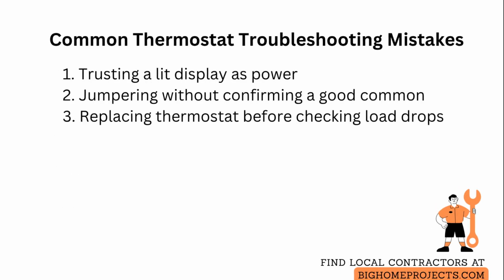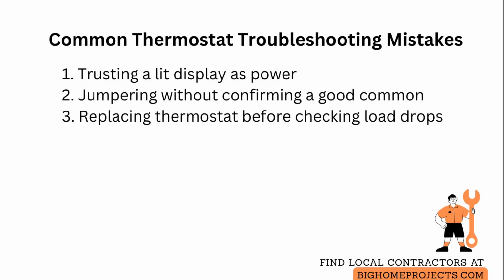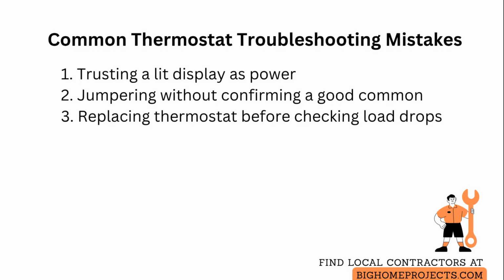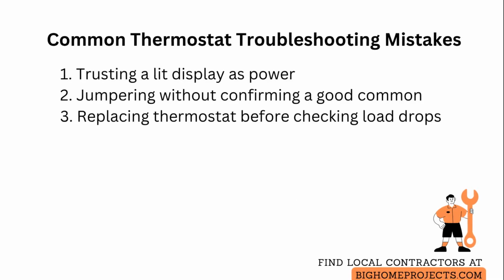The first common mistake is trusting a lit display as proof of live control power, which keeps you stuck on the wall when the real fault is at the furnace or air handler. Pull the batteries and test R to C so the display cannot mislead you.